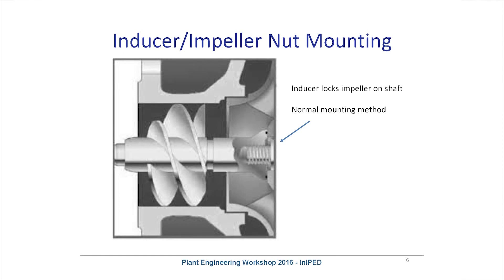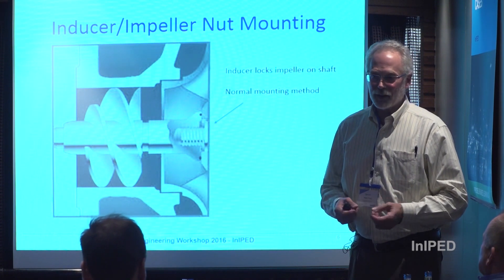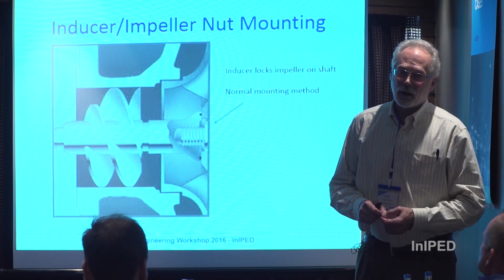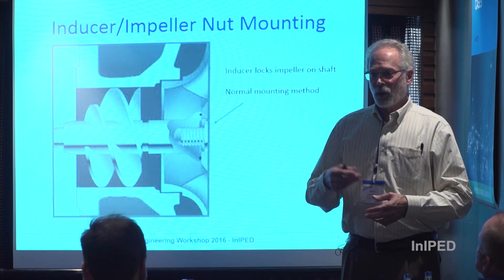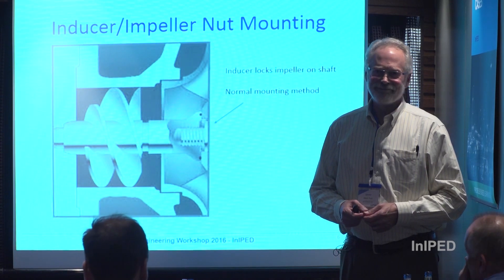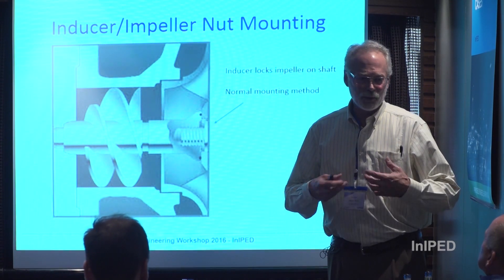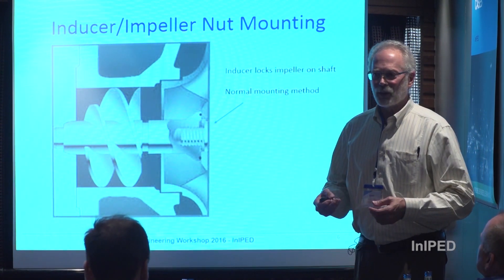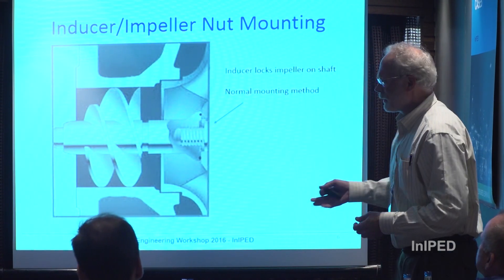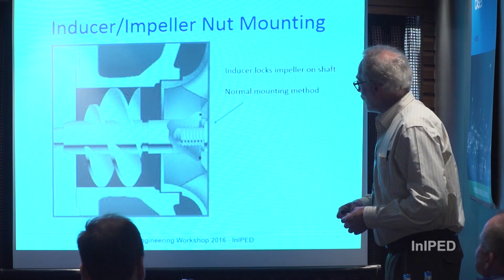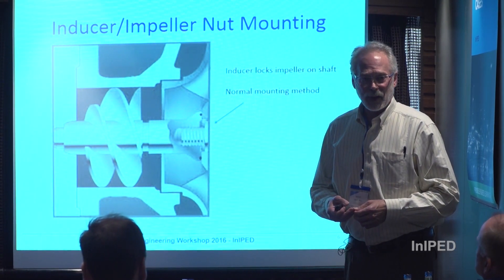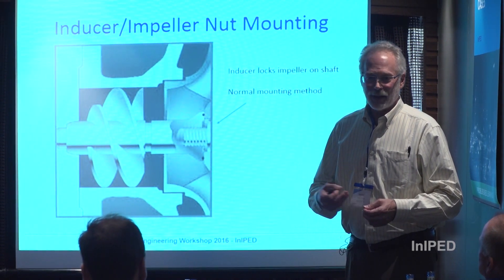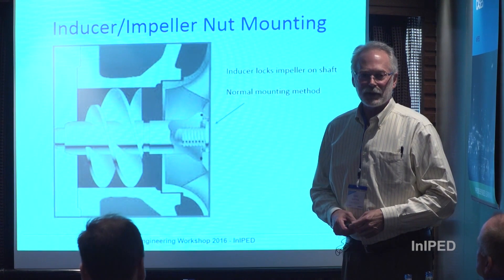There are a number of ways you can mount an inducer to an impeller. One of the most common is to thread it onto the shaft like an impeller nut — either through a stud in the shaft or threads in the end of the shaft. That's perfectly common, but there are restrictions. Once the torque gets up — say around 2,000 gallons per minute or 500 cubic meters per hour — you're asking that threaded shaft to do a lot. You also wouldn't want to use this in severe duty: if the pump is cavitating all the time with lots of vibration, it's probably not your best choice.